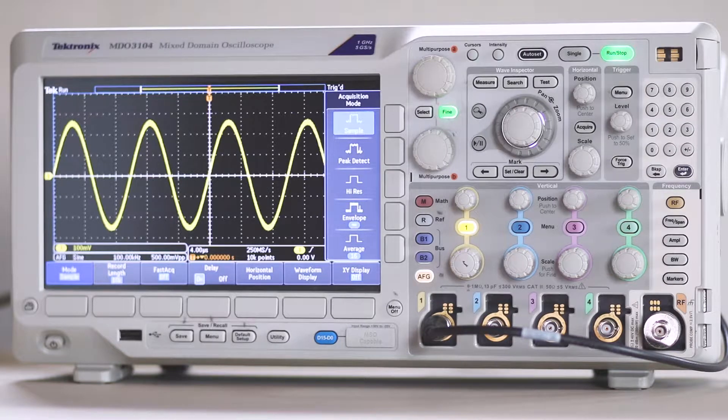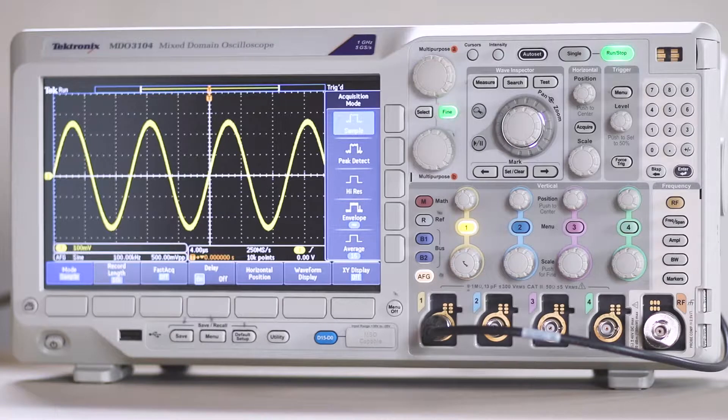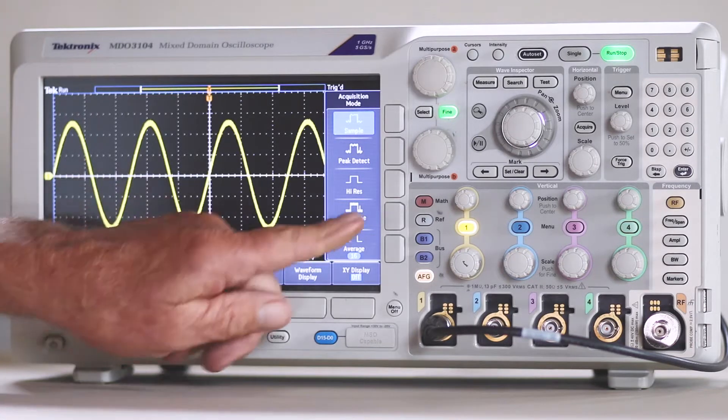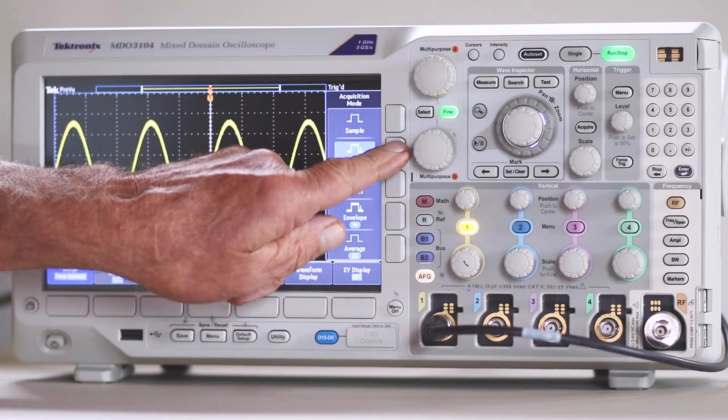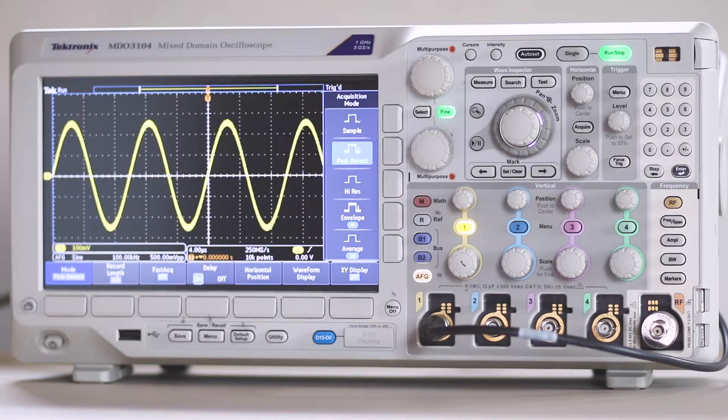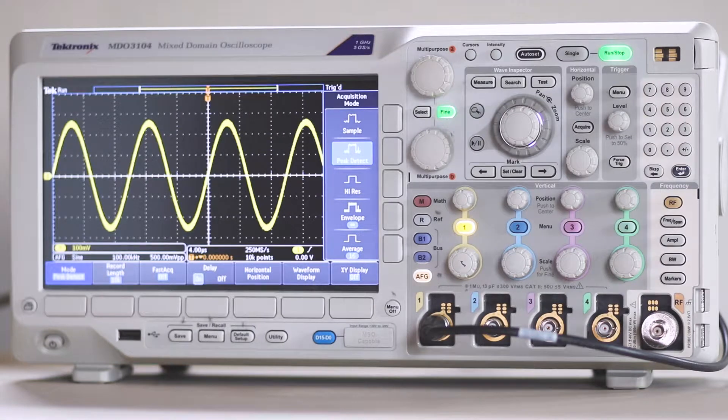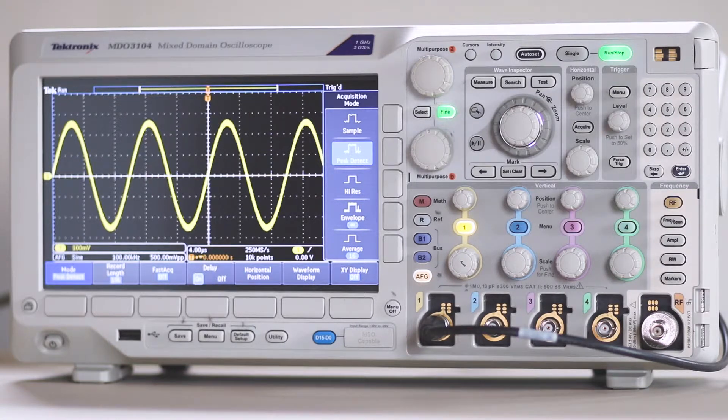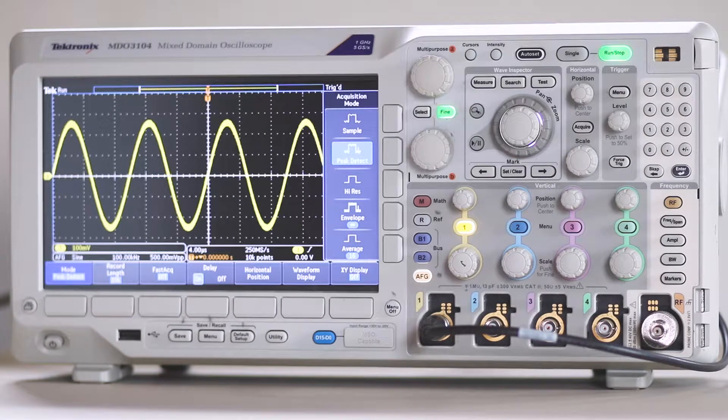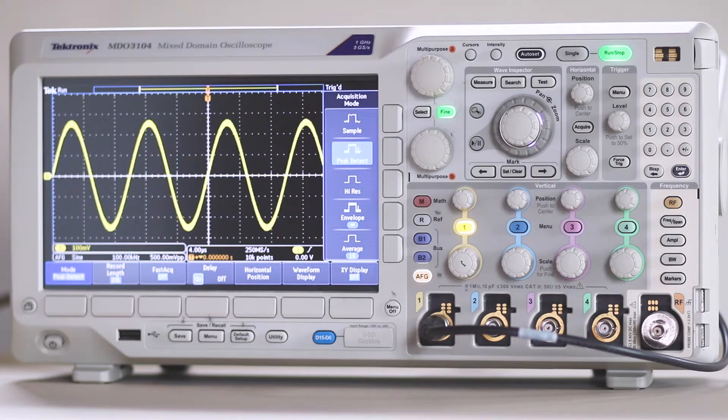Another acquisition mode, this one working only in real-time, non-interpolated sampling, is Peak Detect. It uses the highest and lowest of all samples occurring in the consecutive acquisition intervals.